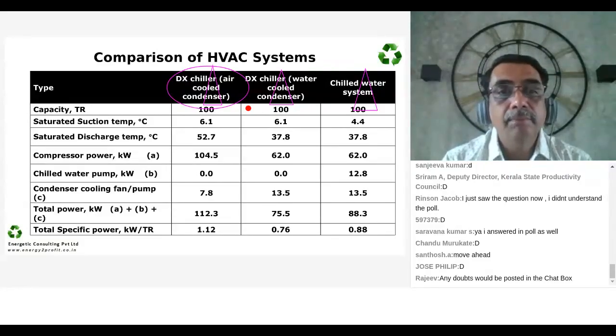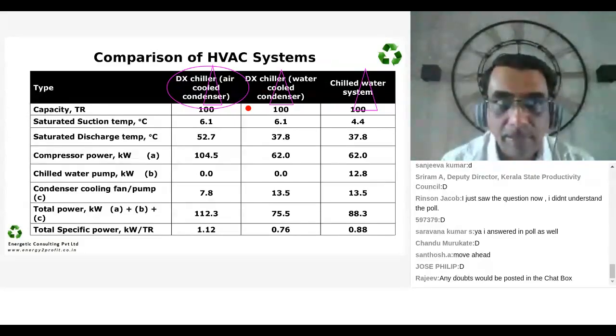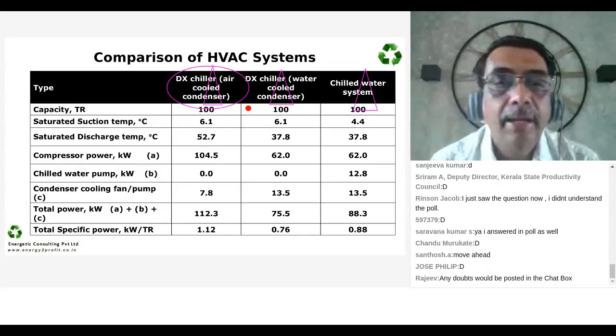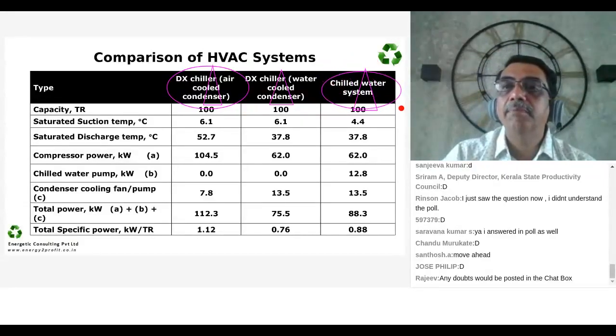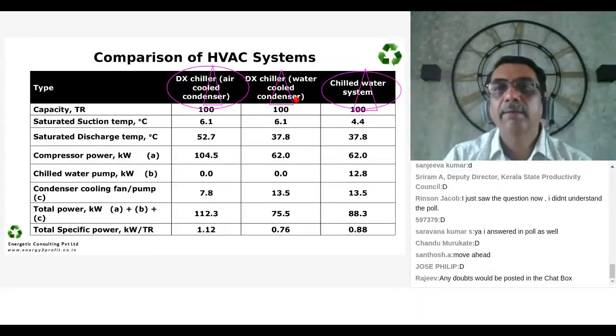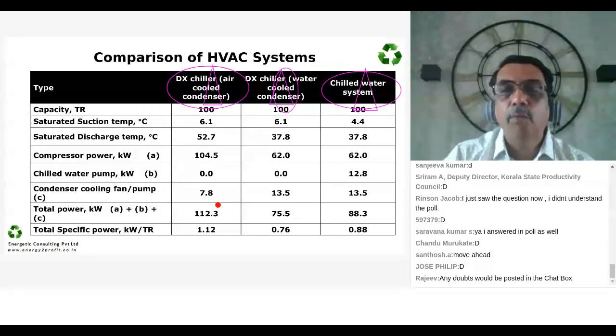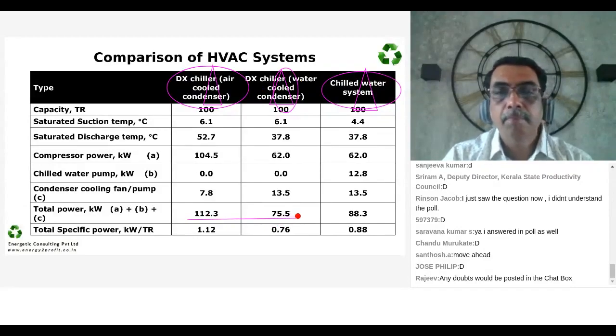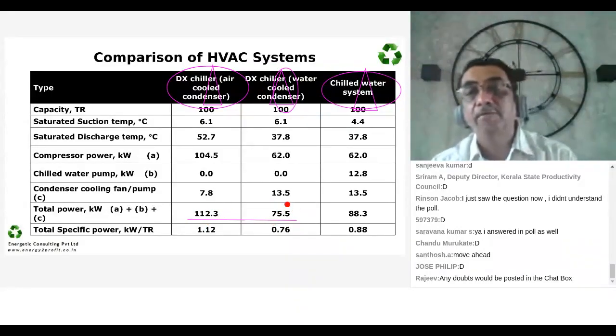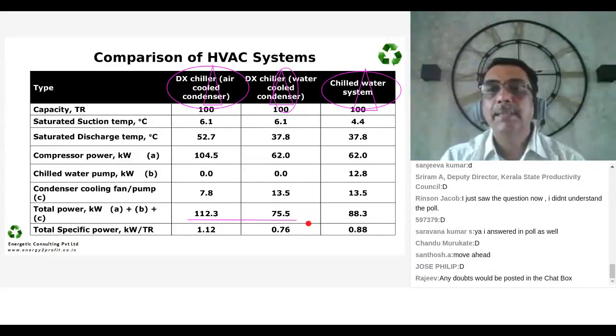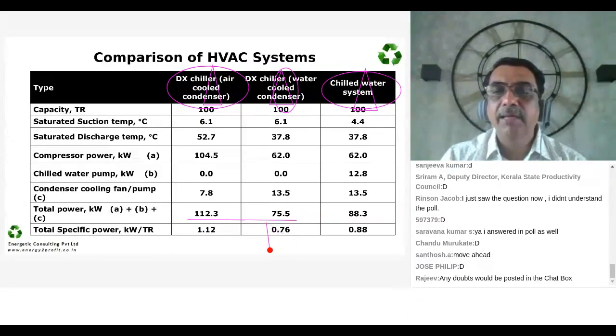On the chilled water side, which means the central system, you can have air cooled as well as water cooled systems. Very few chillers are with water cooling. Generally, they are air cooled. But I've still made a comparison of DX air cooled and water cooled. You see the difference here. Significant difference, right? I'm saying the air cooled one is 112 and the water cooled is 75. Significant difference. And they are the best in the category. A lot of people feel that air cooled systems may not be efficient. That's not true. They are efficient.